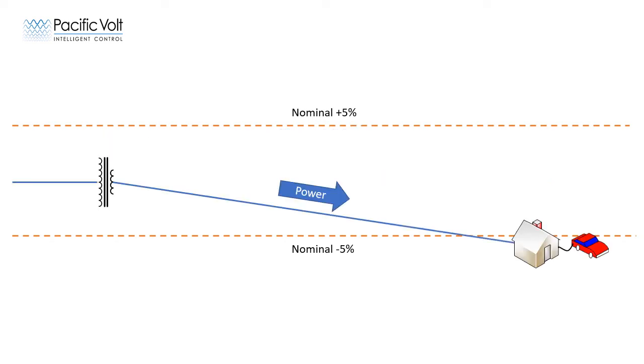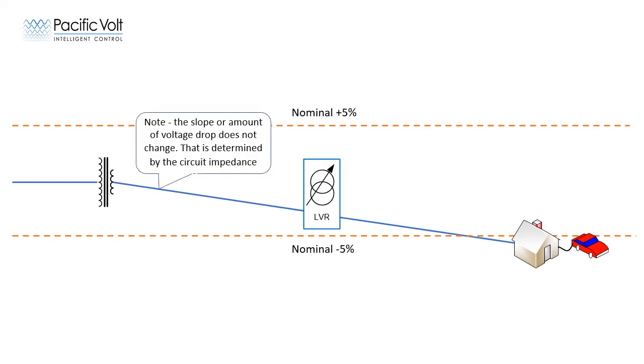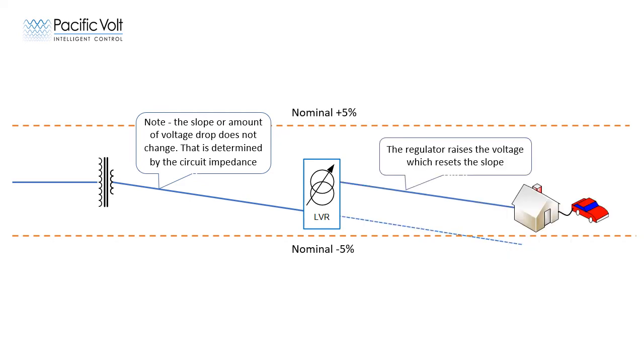Conversely, during higher than normal loading, such as during EV charging, the LVR can raise the voltage to maintain voltage compliance. Note that for a given power flow, the amount of voltage drop on the secondary does not change. The LVR just raises the voltage at its output in order to maintain compliance at the building.